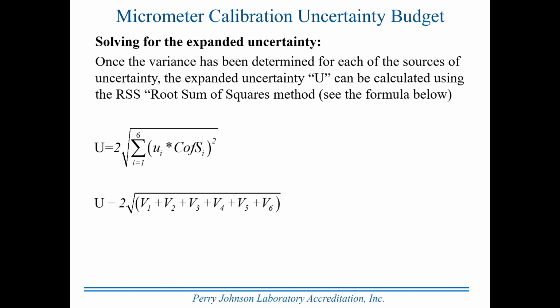Here's what the equation actually looks like, with V representing each contributor, V1, V2, V3, all the way to V6. So you have the variances are the standard uncertainty multiplied by the coefficient of sensitivity, and that product squared. That would be true for V1, V2, and so forth. So you add those together, take the square root of that, and multiply it by 2. So when you take the square root, you now have the combined standard uncertainty, and you multiply it by whatever coverage factor you've chosen. And in most cases, it's going to be 2. 2 times the combined standard uncertainty gives you the expanded uncertainty, capital U. So at that point, you've got the uncertainty.